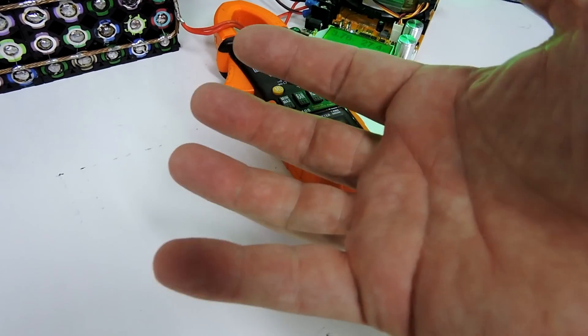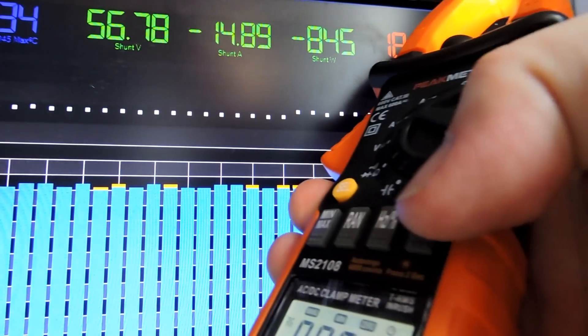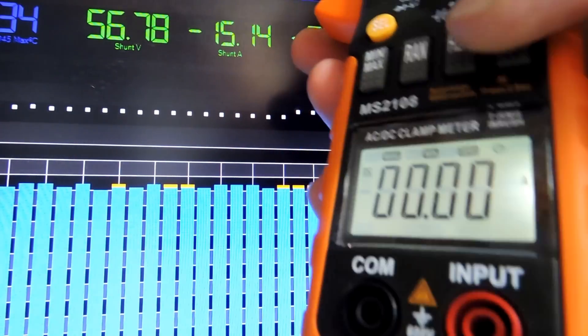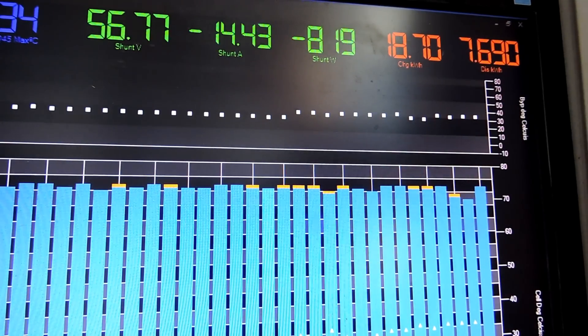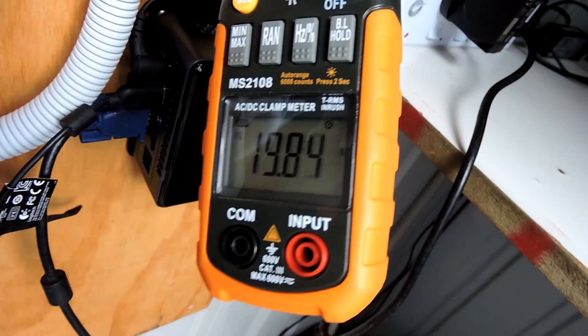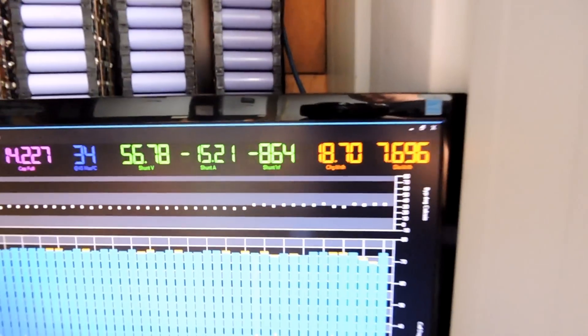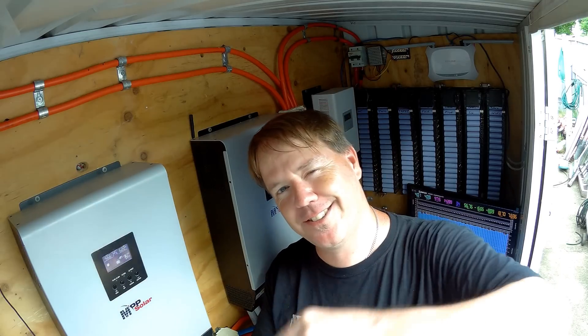Let's take it down to the battery shed. We worked out how to get the backlight on — hold the BL button for two seconds. It shuts down again after a while. The backlight works, and there's a little light there too — handy! It's doing about 15 amps on the computer screen, but the clamp meter is displaying about 20 amps, so it's not perfect. I'm going to put my money on this meter being out rather than the Batrium.